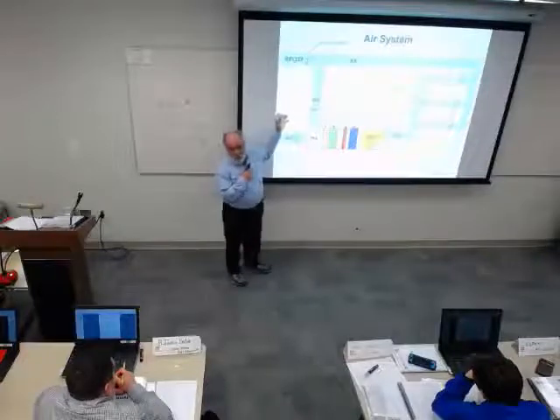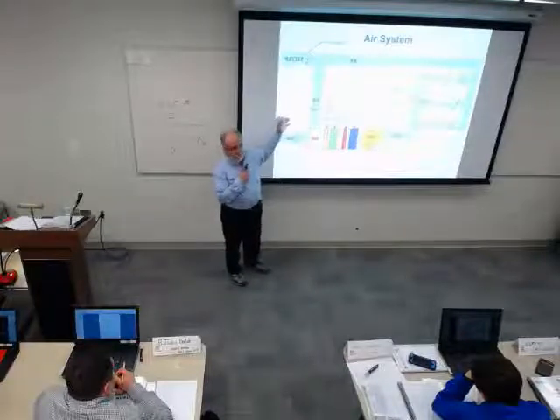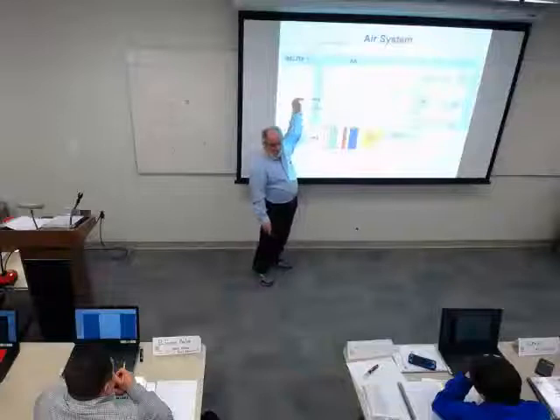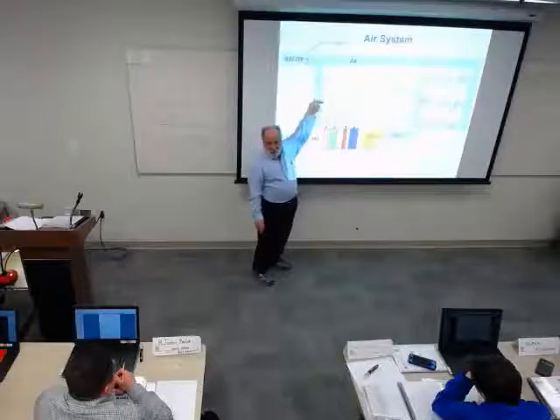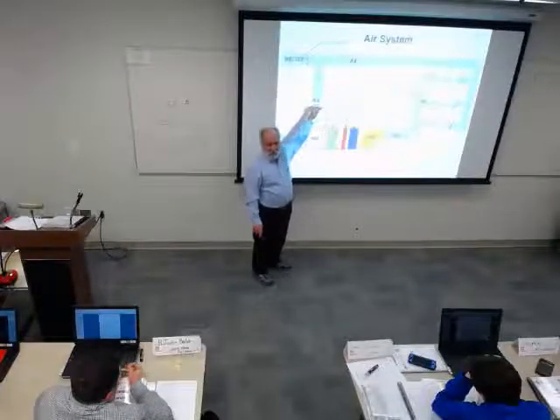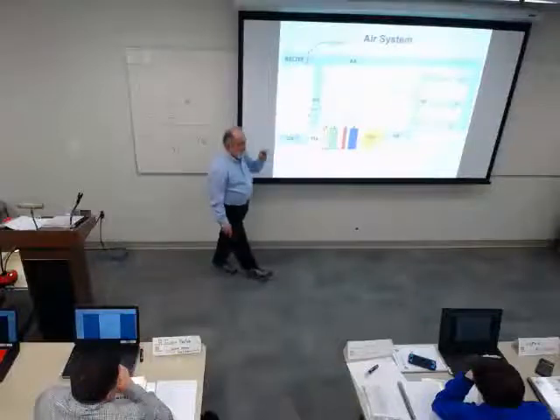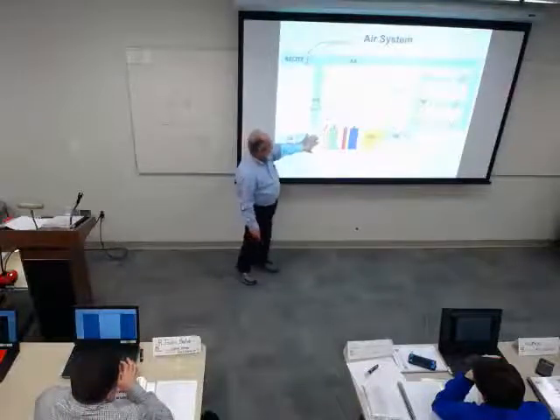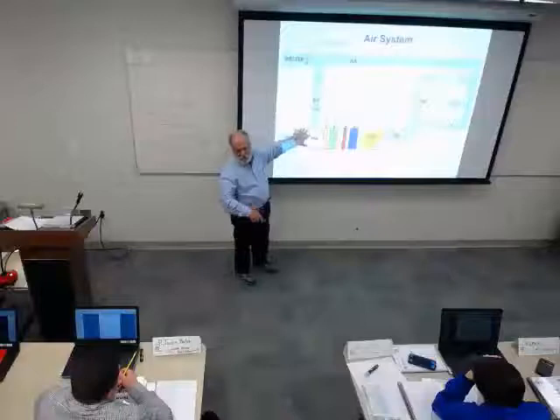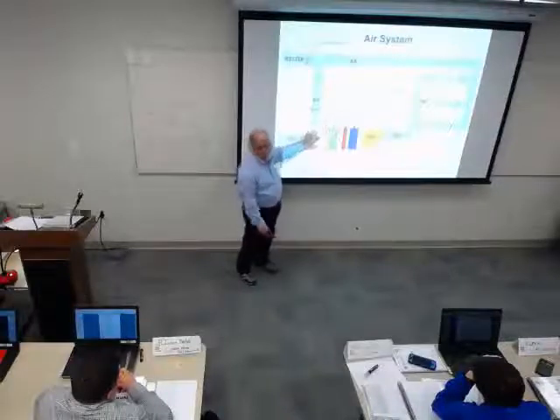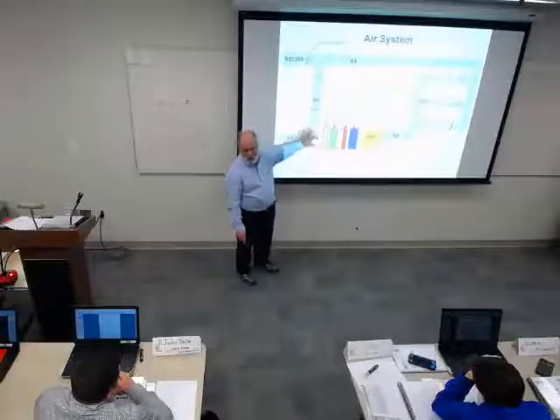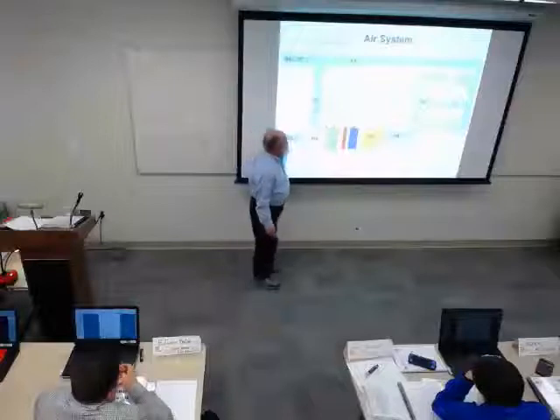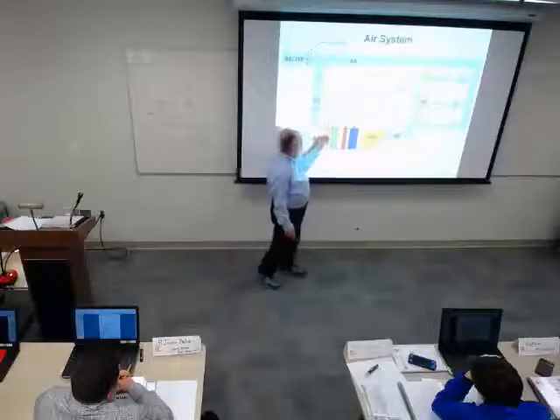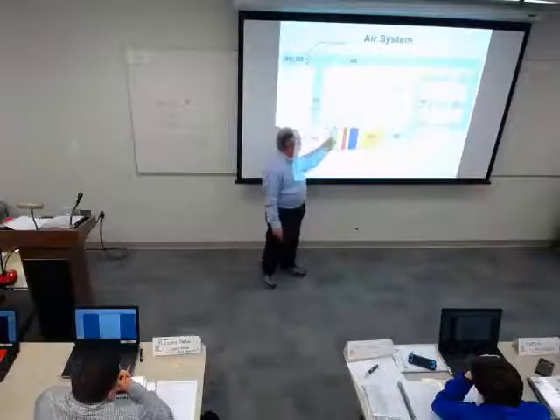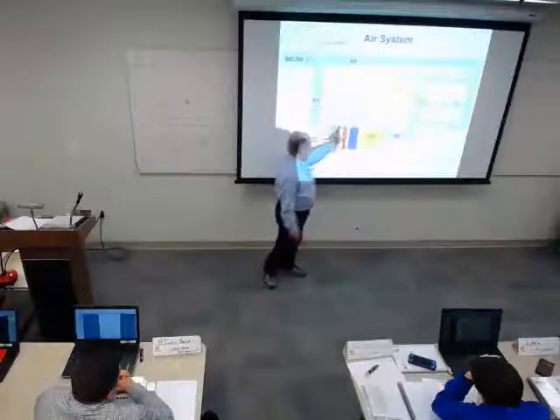If at all possible, and you have any choice about what's going into the project, try to get them to bring it in the duct before it gets to the air handling unit, so you've got room to mix. You might have a facility to promote mixing, because I've got some funny stories about mixing I can tell after class. This is a place where it often happens. So we take it through the filter. This is usually a MERV 8. That's a MERV 13 now.